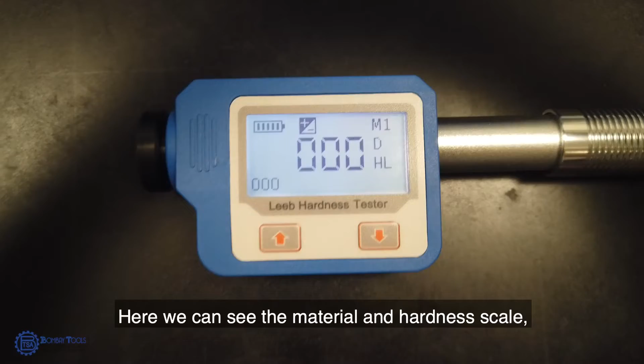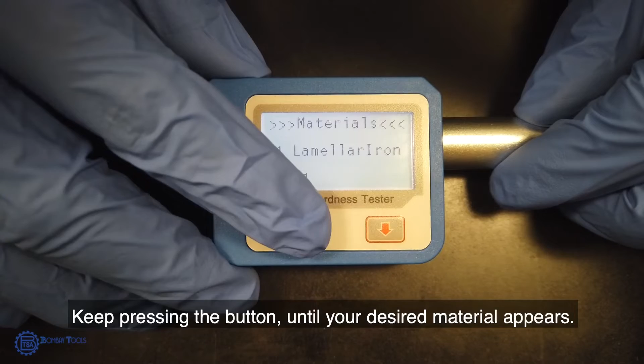Here we can see the material and hardness scale that has currently been selected. This can be changed by accessing the menu by long pressing the down button. The first menu option is material, and we can change the material by short pressing the up button, which will cycle through the various available material options. Keep pressing this button until your desired material appears. In this case, let us choose forged steel. Now press the down button to go to the next menu.